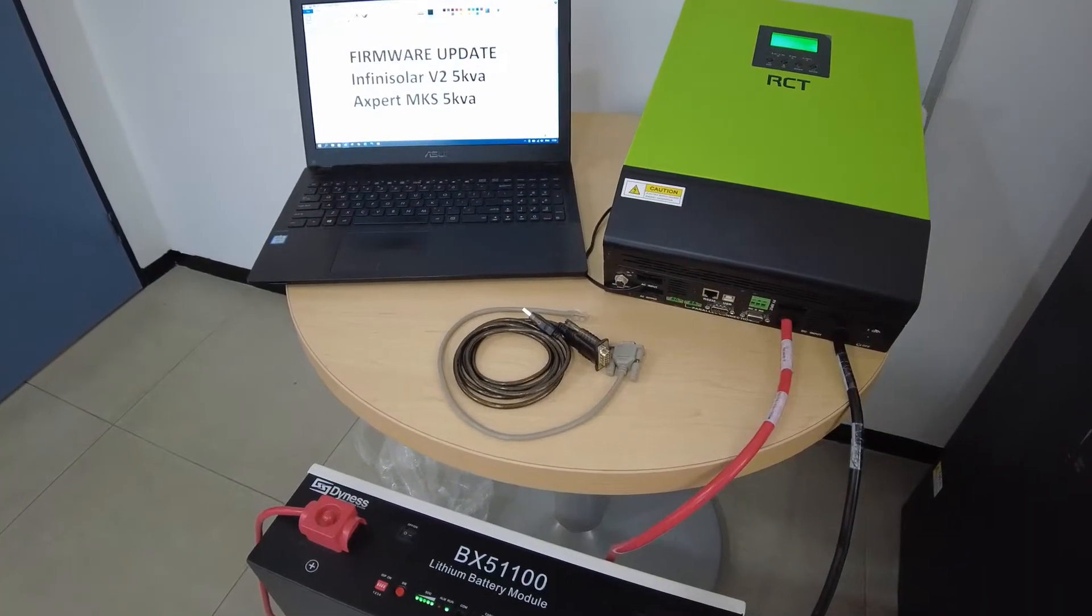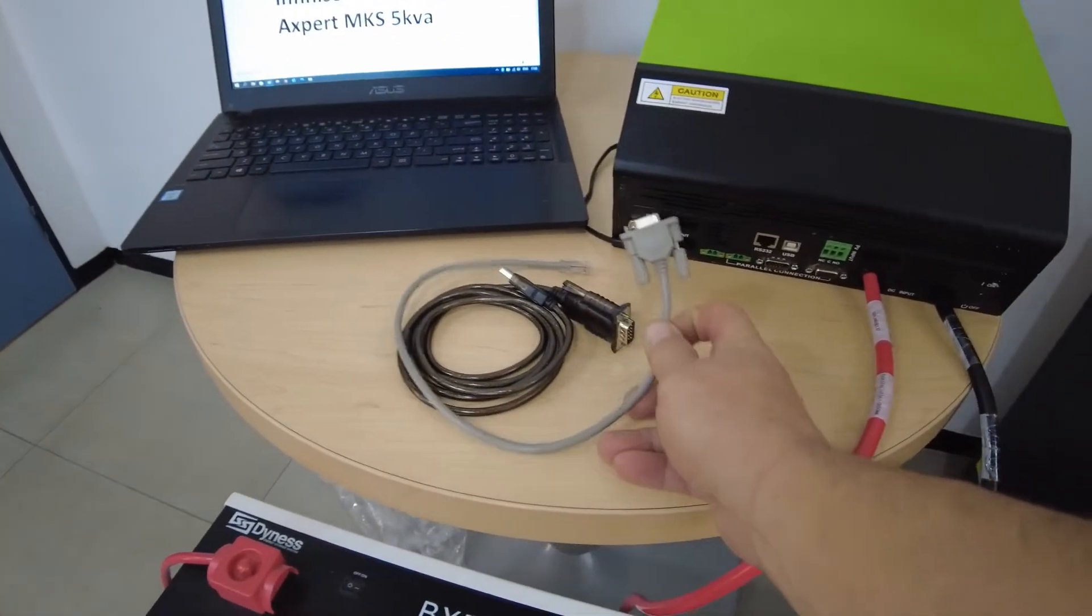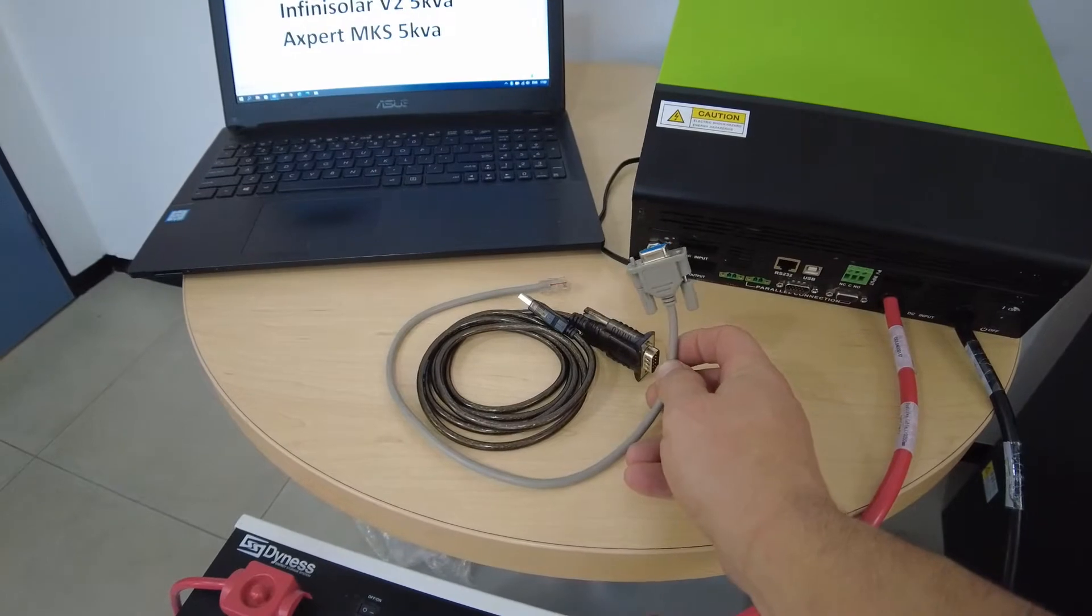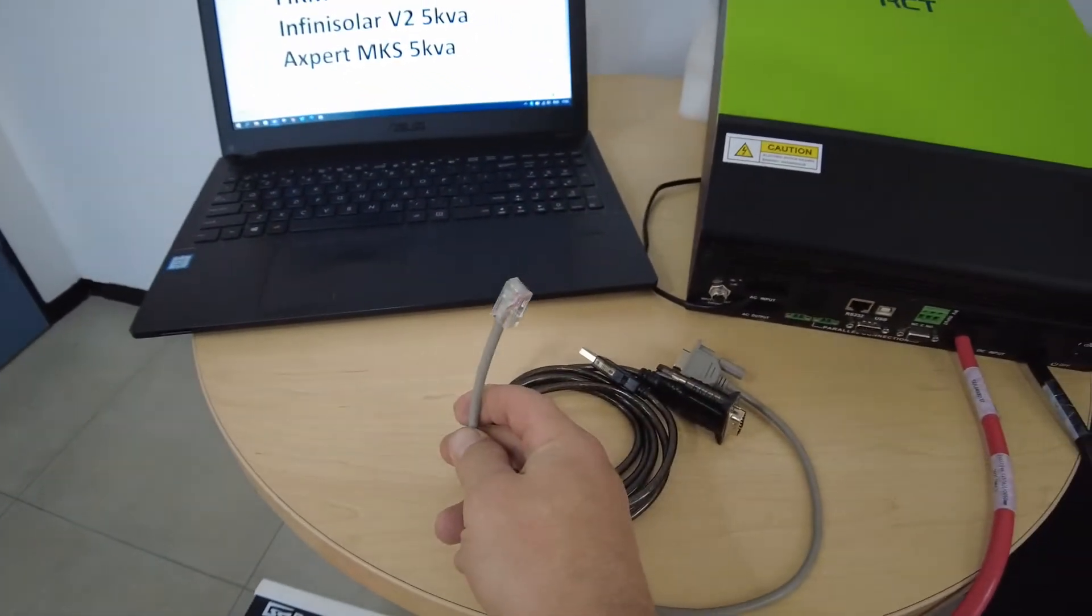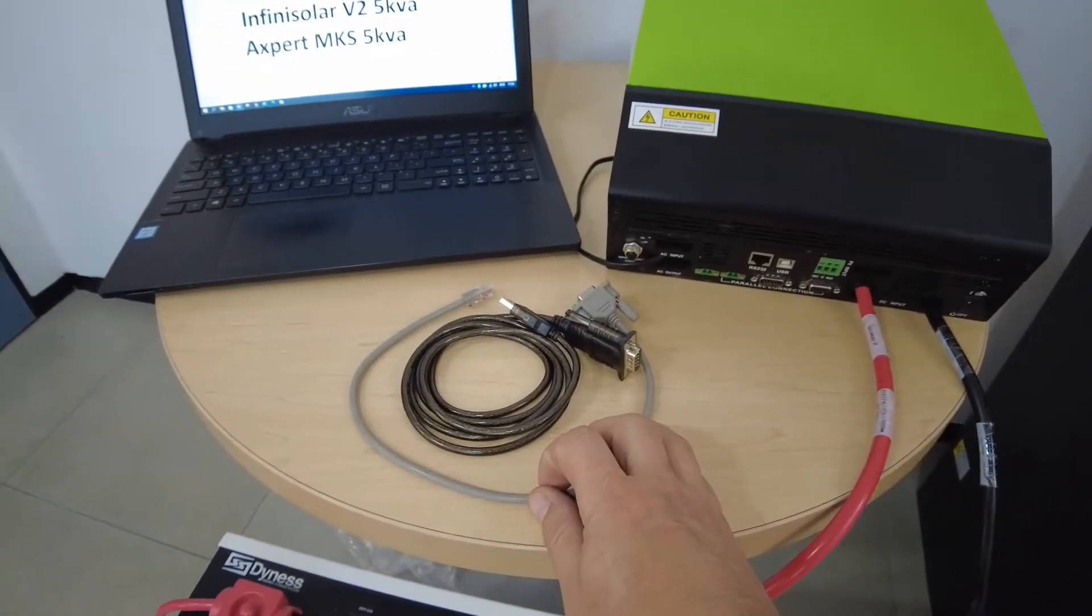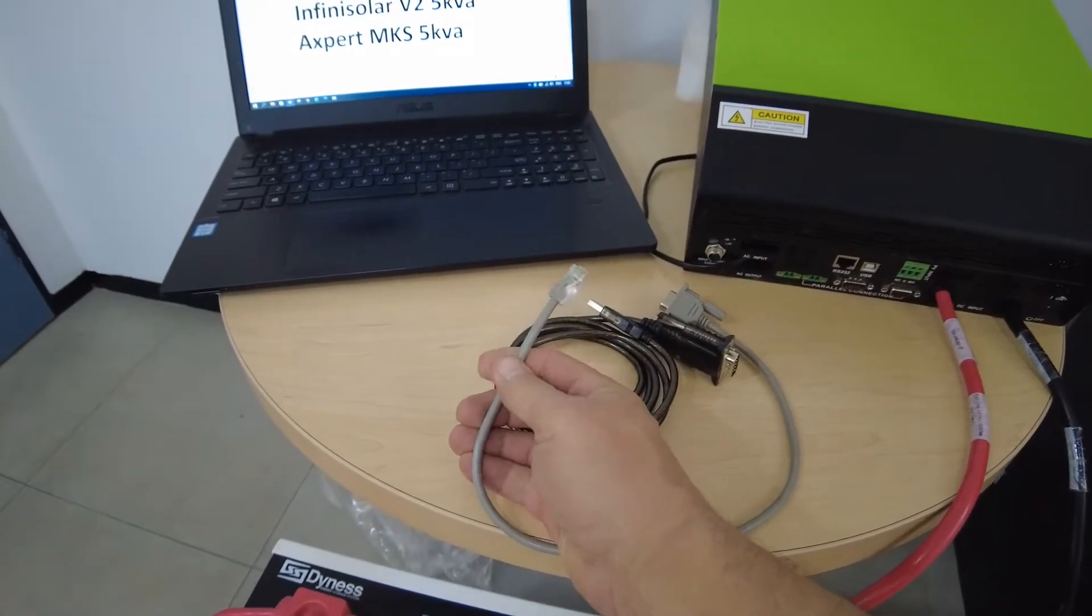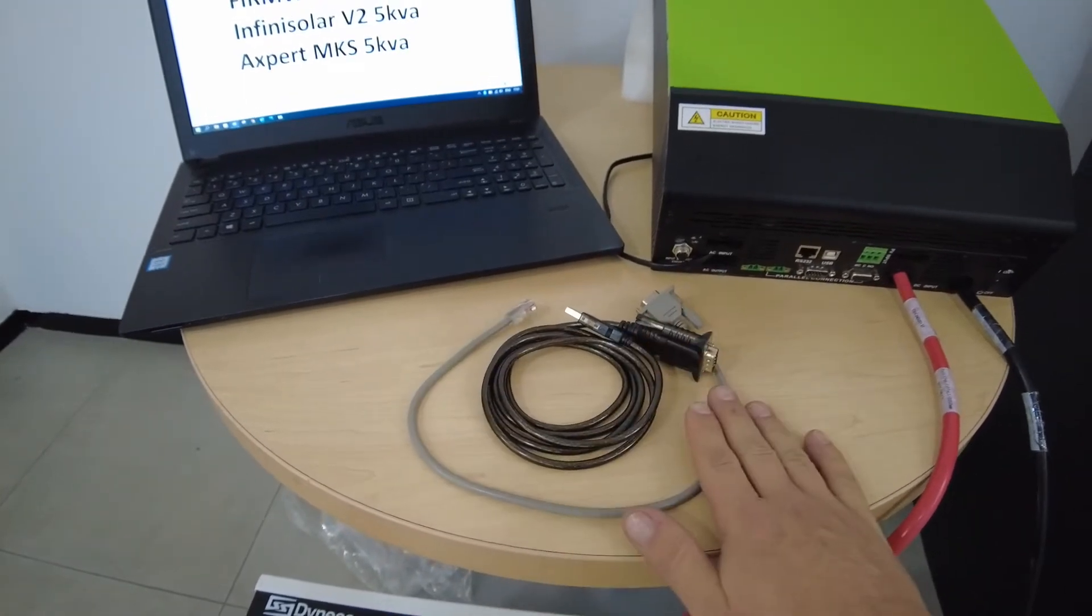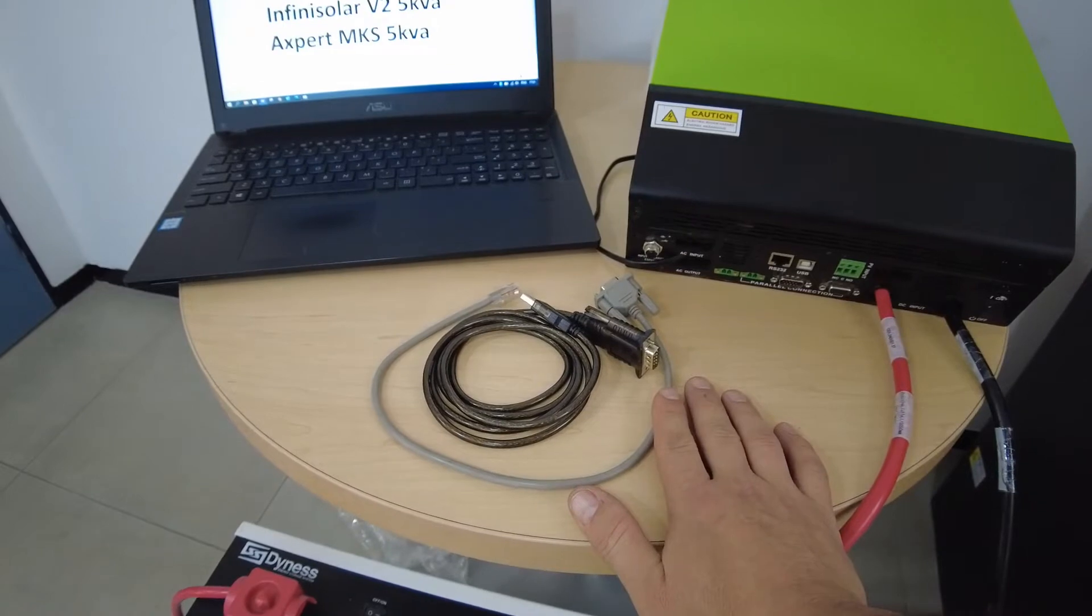So let's look at the cabling first. With the RCT Inverters you always get this communications gray cable with the serial port on one end and the RJ45 on the other end. This is a standard communications cable for the RCT Inverters. Note it's not a standard cable that you will buy online. The pinout is different on those cables. You have to use the cable that came with the inverter.